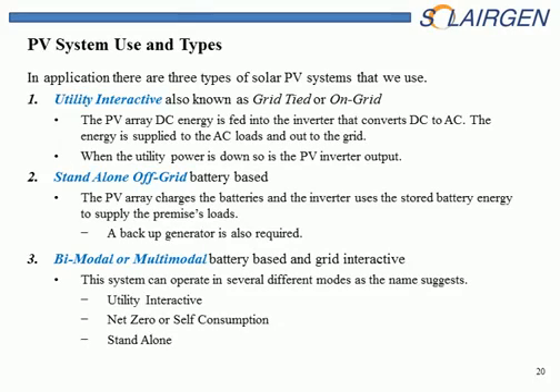A standalone off-grid system is different. It is internally fed from a battery bank, so whether it's connected as a bimodal, which would have a battery bank and be connected to the grid possibly, or if it's a standalone, there is the potential of this energy being present whenever the utility power is off. Bimodal systems, we refer to these as utility interactive, where they actually can sell back to the utility. When the power goes off, it becomes a standalone system.